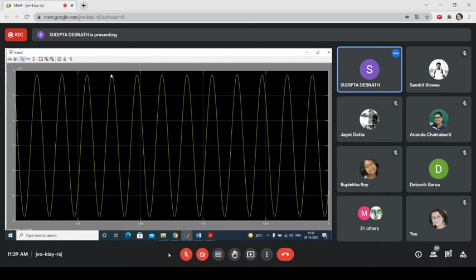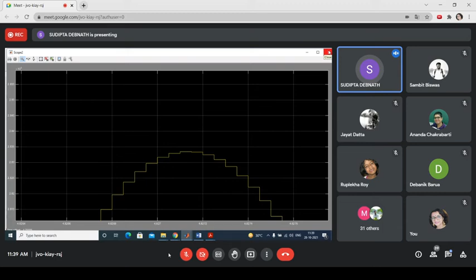For 800 megawatt, another will observe for 1000 megawatt. So 1000 megawatt, we will put it as 1000. We will observe that the receiving end voltage is still less because the power is increasing. What is the value? Value is almost 283. You write down 283. So instead of 326.6, it becomes only 283 kV.